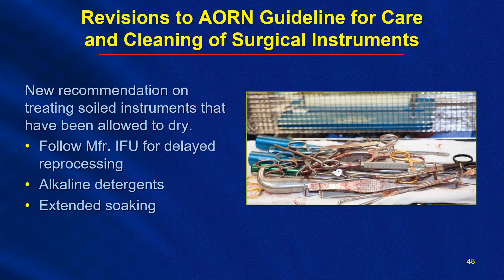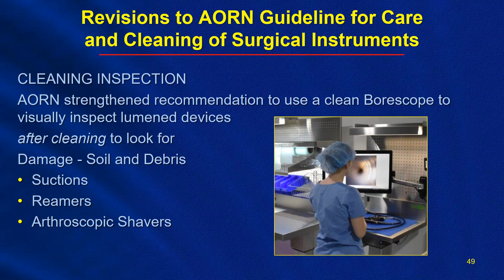And for cleaning inspection, AORN strengthened the recommendations to use a clean borescope to visually inspect lumen devices after cleaning, basically looking for any damage, any soil, any debris, and things such as reusable suctions, reamers, cannulated reamers in orthopedics, arthroscopic shavers, anything that has lumens, to look for visible soil, and then again to use the other verification methods to support that things are truly clean.